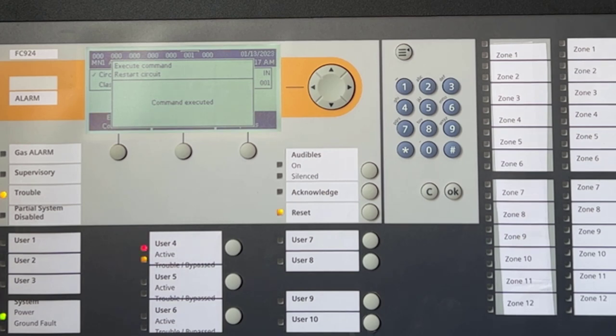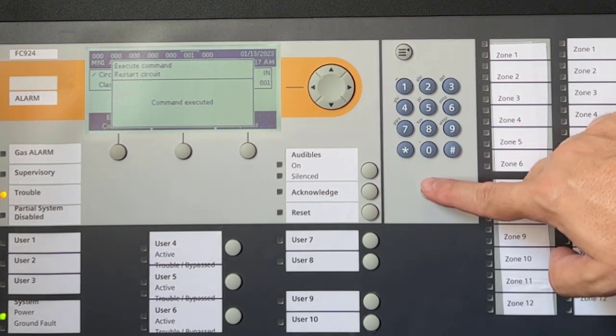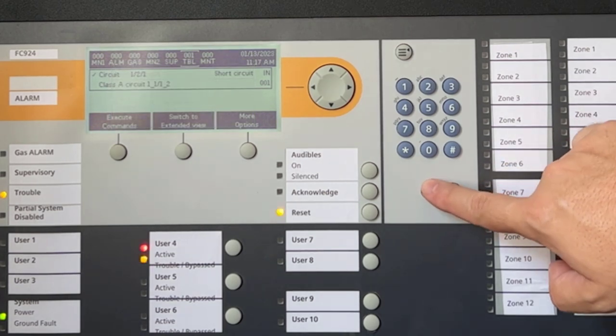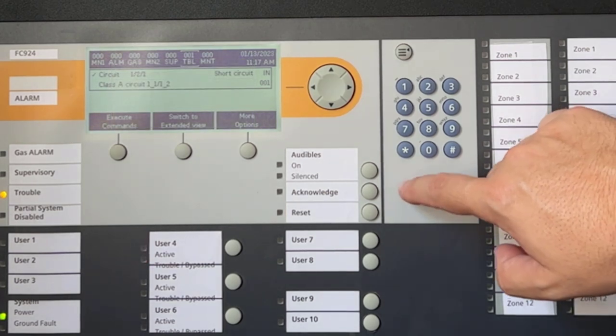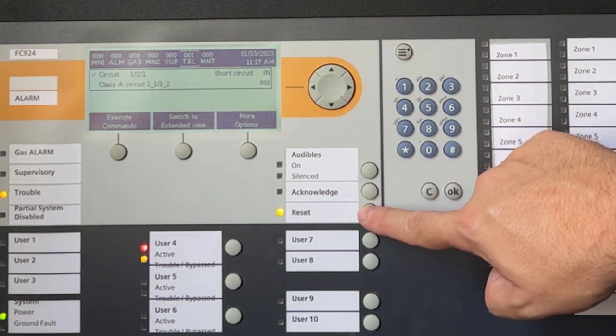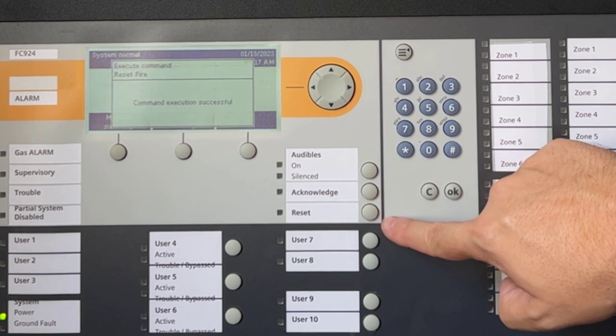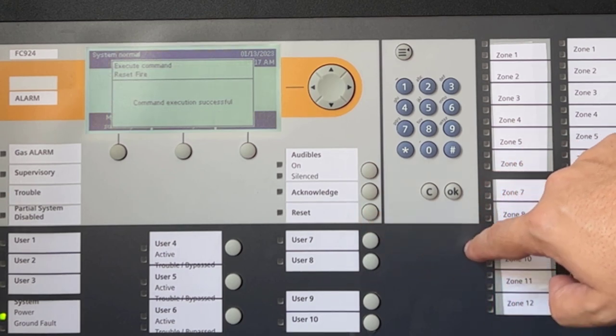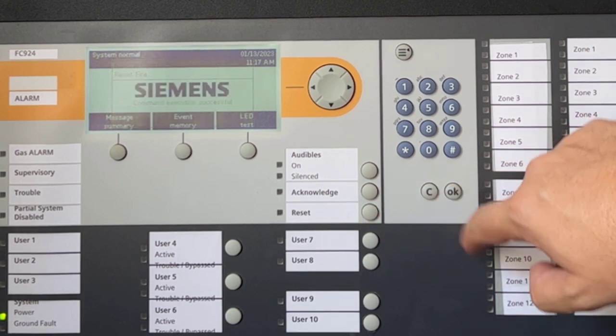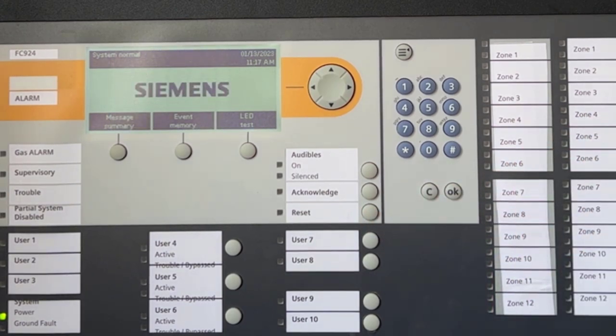It is important to understand this, as it can become a troubleshooting nightmare if you believe you have fixed the problem, but the panel is still showing a short circuit trouble and you forgot that you have to restart the actual circuit.